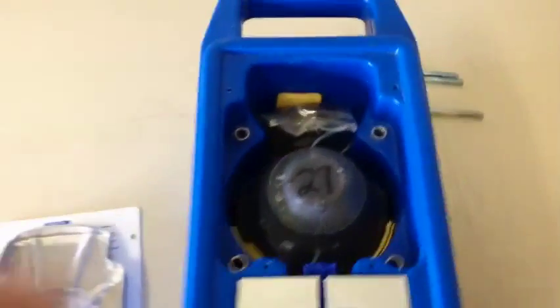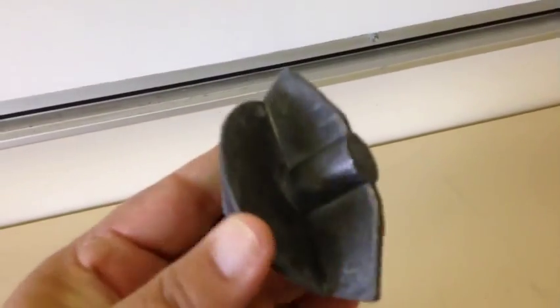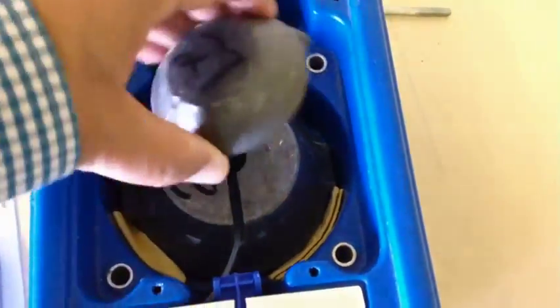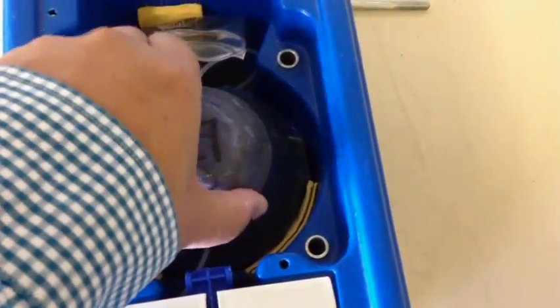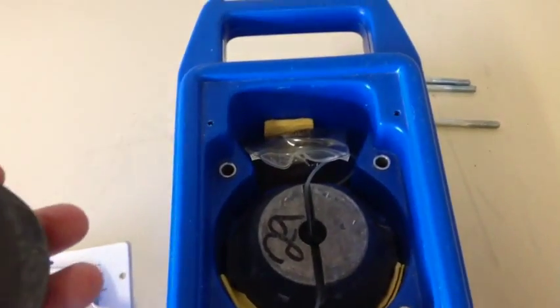So I'll put you down for two seconds. What we've done is I've wedged that out, and what you end up with is this lead cap. This lead cap is shaped to fit into these grooves to prevent any kind of leakage. It slots into that groove and seals all the potential leakage of radiation—not liquid leakage, but photon emissions and particulate emission.